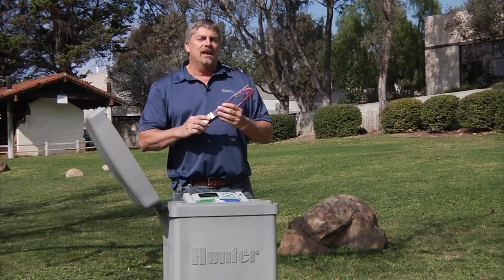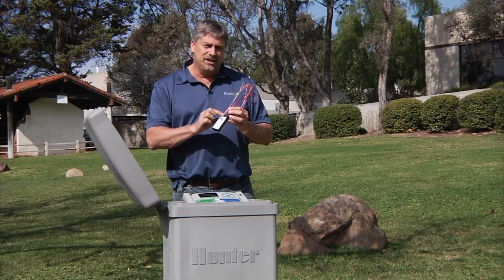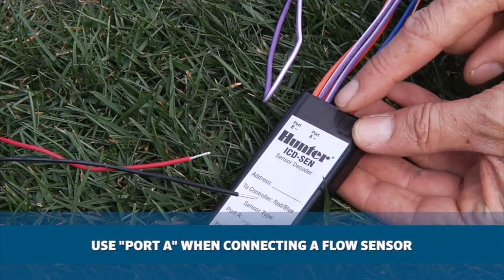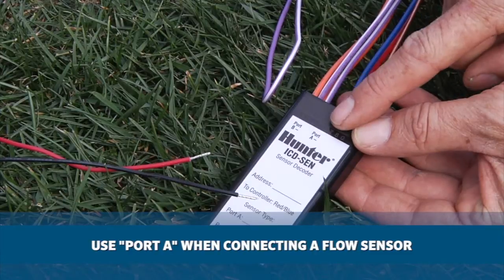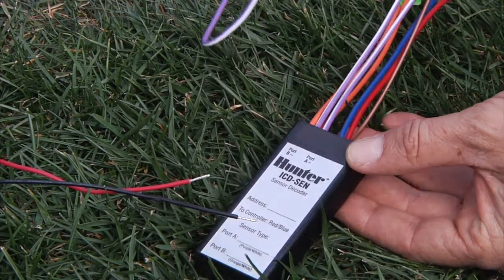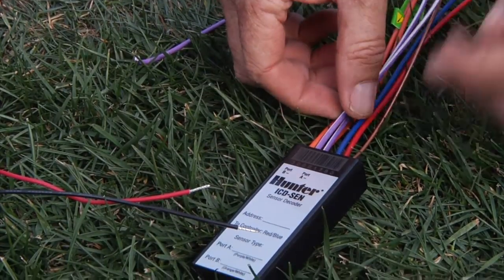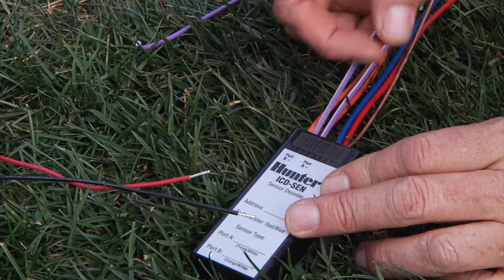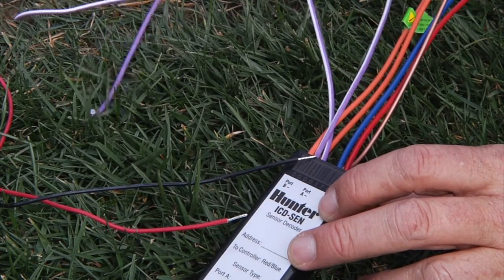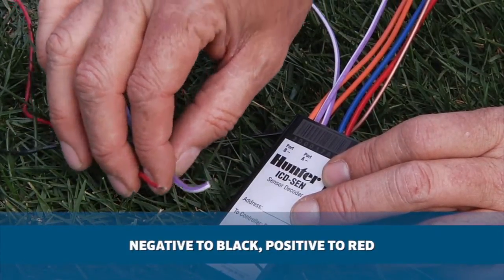Connecting a sensor decoder to the two-wire path is just the same as you would a station decoder. The big difference is you have to pay attention to ports A and B on the sensor decoder so that when they hook up to the sensor, you use the correct wires. When connecting a flow sensor to an ICD-SEN, you have to use port A. You'll notice on the front it says port A negative. You've got a loop of two purple wires coming out of the top of the decoder. Simply cut the loop so you've got two individual wires. Take the front purple wire, which is the negative port, and attach it to the black wire on your flow sensor. The back purple wire is the positive port, so attach it to the red wire on the flow sensor. Polarity does matter — negative to black and positive port to red.